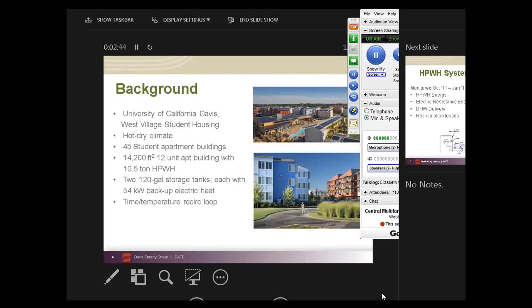There are 45 student apartment buildings, each with 12 units. The building that we monitored had 36 bedrooms, but there's about 2,000 individual bedrooms on site. The buildings are 14,200 square feet and served by a 10.5-ton heat pump water heater with electric resistance backup. The backup consists of two 120-gallon electric resistance heaters that are 54 kilowatts each. The building was also served by a recirculation pump that was both temperature and timer controlled.